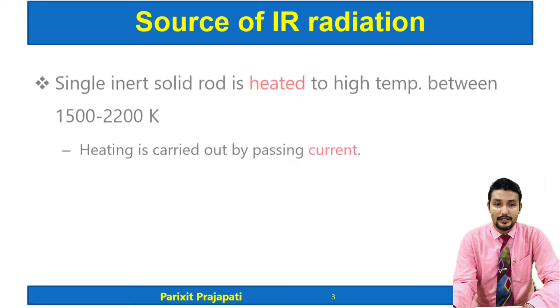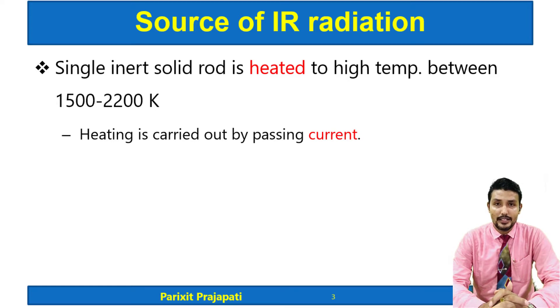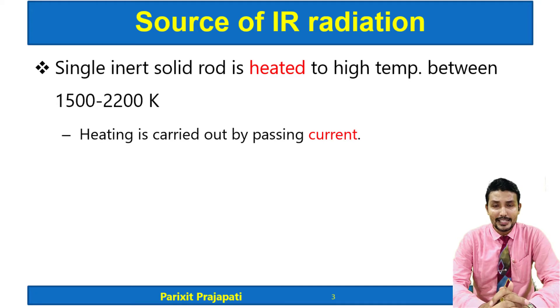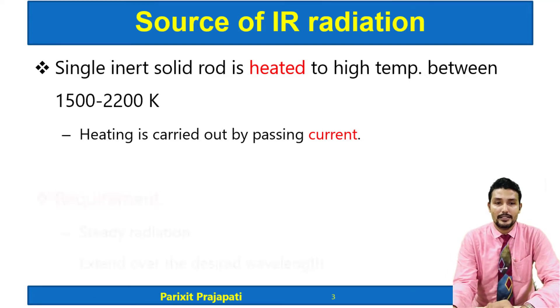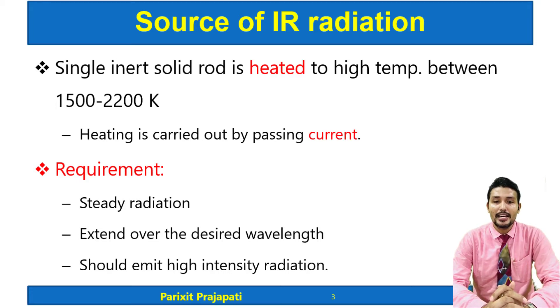The source of radiation needs to provide IR radiation. It is a solid inert solid rod heated at high temperature between 1500 to 2200 Kelvin by passing electrical current. When heated, it produces energy in the form of heat as well as radiation, and that radiation is IR radiation. The ideal requirements of any IR radiation source are that it should produce continuous and steady radiation and extend over the desired wavelength.